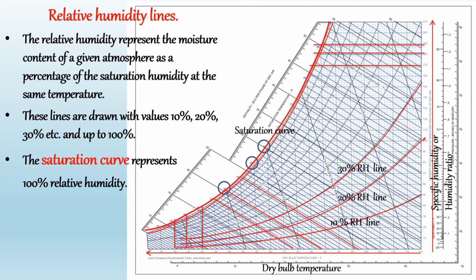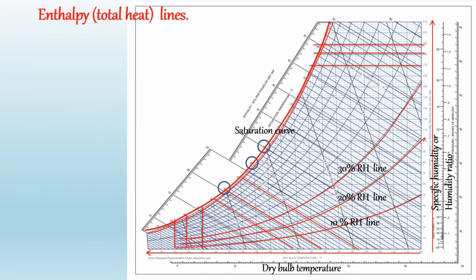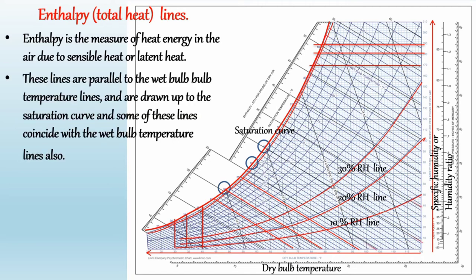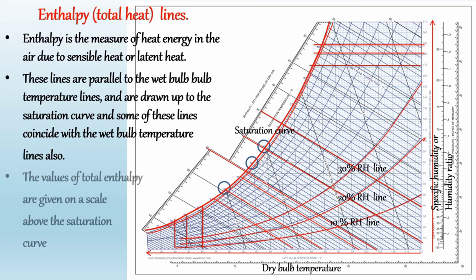The next line is the enthalpy or total heat line. Enthalpy is the measure of heat energy in the air due to sensible heat or latent heat. In the psychrometric chart, the enthalpy or total heat lines are inclined straight lines and uniformly spaced. These lines are parallel to the wet bulb temperature lines and are drawn up to the saturation curve. Some of these lines coincide with the wet bulb temperature lines. The values of total enthalpy are given on a scale above the saturation curve.